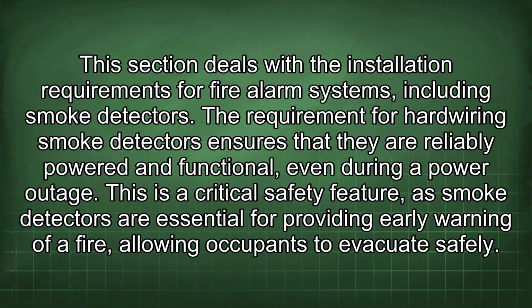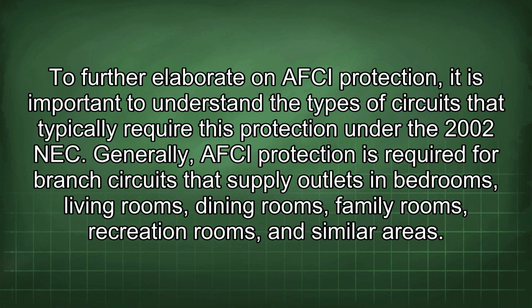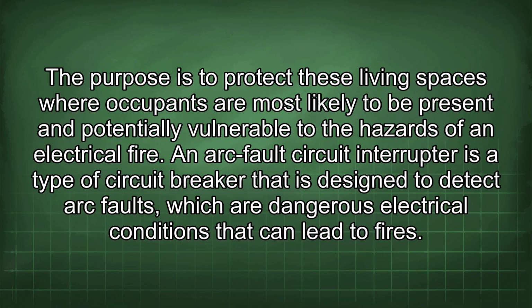to evacuate safely. To further elaborate on AFCI protection, it is important to understand the types of circuits that typically require this protection under the 2002 NEC. Generally, AFCI protection is required for branch circuits that supply outlets in bedrooms, living rooms, dining rooms, family rooms, recreation rooms, and similar areas. The purpose is to protect these living spaces where occupants are most likely to be present and potentially vulnerable to the hazards of an electrical fire.